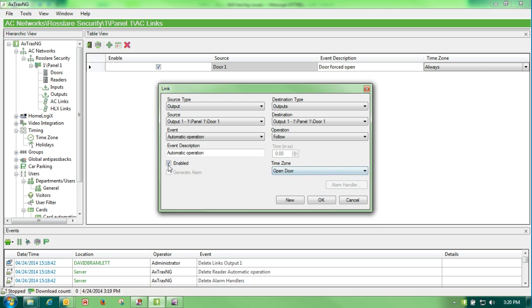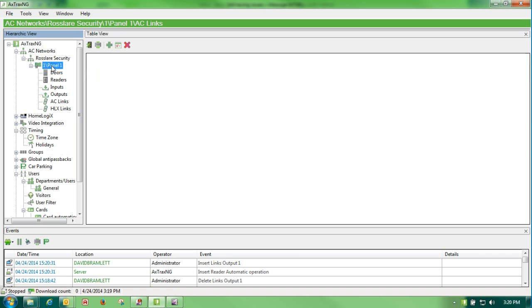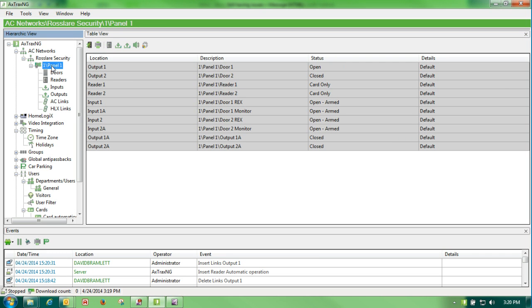And make sure that it's enabled. Tell it OK. And you can see at the bottom here that I've created it. And you can hear your relay open as soon as that happens. To verify it you would just go to highlight your panel. And now you can see that my status is open and that I have created that link.